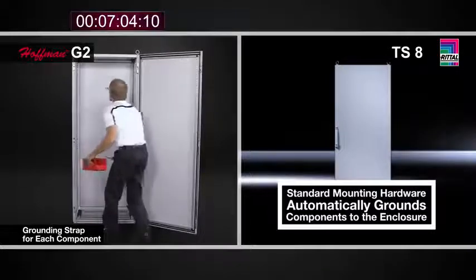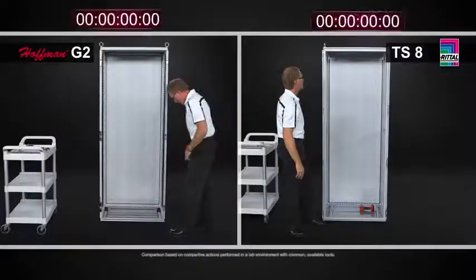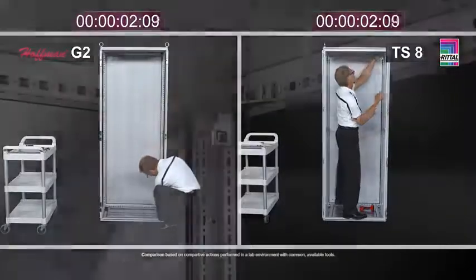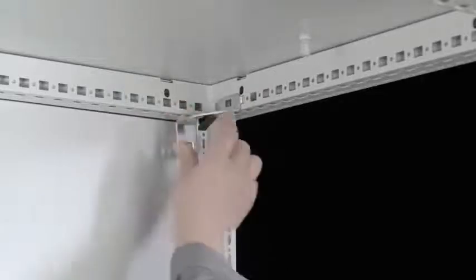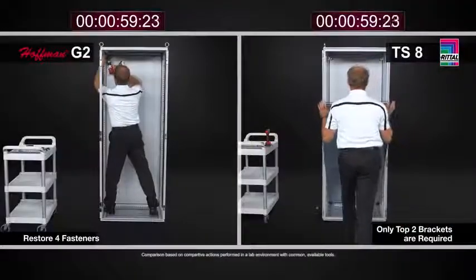Another thing you may do to gain both usable depth in the enclosure and the ability to put more weight on the panel itself is to put the panel in what's called the rearmost position — the furthest position that the panel could be placed in the cabinet. To do that with the Rittal TS8, once you've removed the panel, you simply take the top brackets, which are a tool-less clip — I don't need any tools, I simply use my fingers to undo the clip. I move the top brackets back. The brackets that held the mounting panel at the bottom are no longer needed because the mounting panel feet have a pin in them, and that pin inserts into the frame of the TS8. So I've eliminated some additional hardware that I no longer need when positioning the panel in the rearmost position. Very quick, very simple.